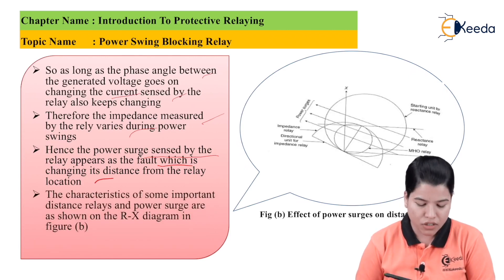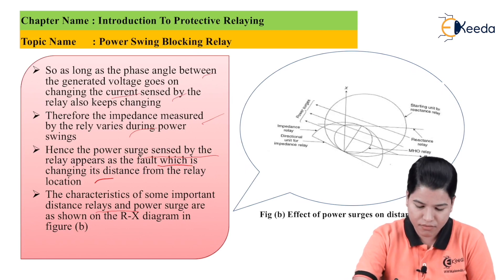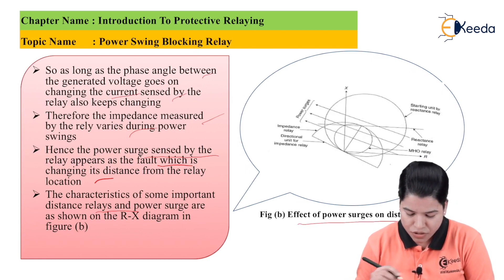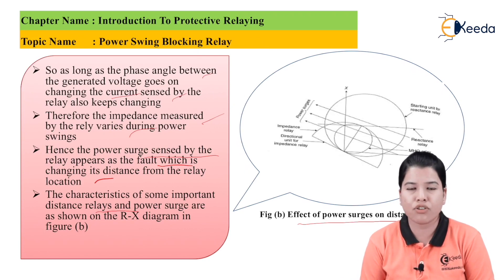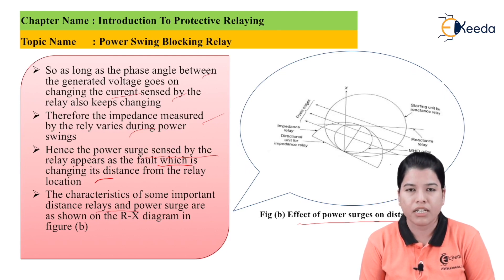Let us consider the characteristic of some important distance relays and the power surges shown on the R-X diagram in figure B. The figure shows the effect of power surges on the distance relay. The distance relay characteristic is better represented on the R-X diagram, and the distance up to which the relay provides protection depends upon the radius of the R-X diagram circle. When the fault occurs within this radius the relay operates; if the fault goes beyond the radius, the relay remains inoperative.